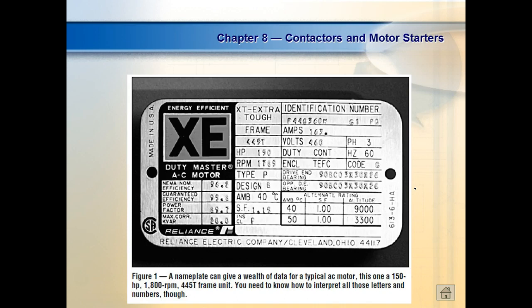Insulation class, and we'll look at the rest of these things. Efficiency. Sometimes it gives us how we can do it. We'll talk about this too. This is new on motors too. Power factor, direction. So this is a newer nameplate. Later on we'll get into the motors section on how to read these nameplates. The only problem is that these things are usually never paper. They might be aluminum foil. A lot of times they're metal. A lot of times when they rebuild the motor, they'll take over the nameplate. You've got to look up generic stuff on it.